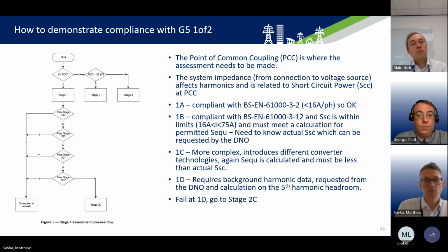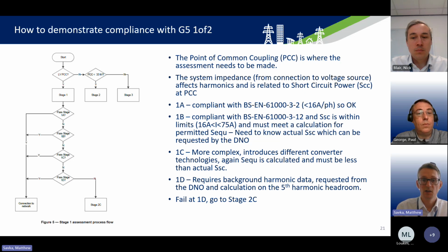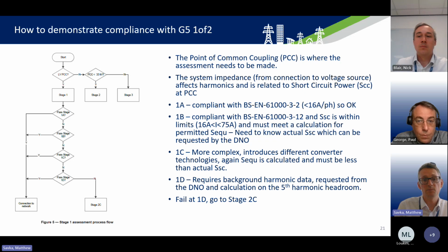So just going on to how to actually demonstrate compliance with G5. It's a staged approach, and if you fail at one stage, you move on to the next stage. Firstly, the point of common coupling is where the assessment needs to be made. That's where the connection is onto our network. And the system impedance from the connection to the voltage source affects the harmonics, and it's related to the short circuit power at the point of common coupling.